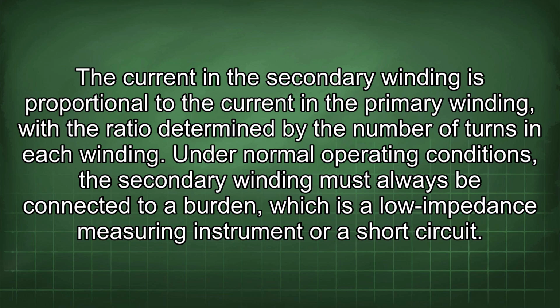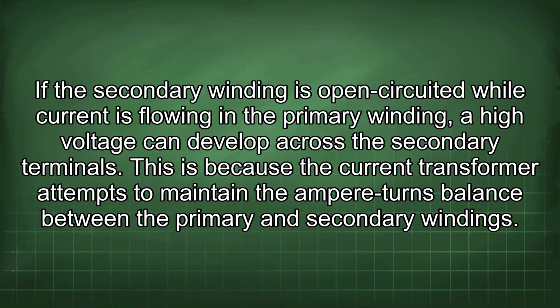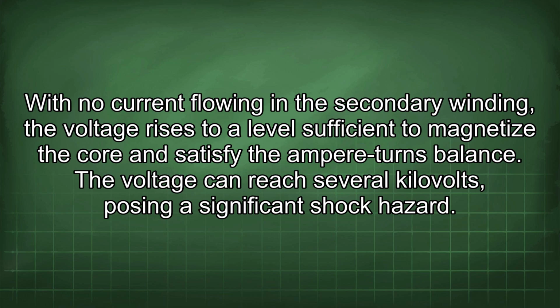Under normal operating conditions, the secondary winding must always be connected to a burden, which is a low impedance measuring instrument or a short circuit. If the secondary winding is open-circuited while current is flowing in the primary winding, a high voltage can develop across the secondary terminals. This is because the current transformer attempts to maintain the ampere-turns balance between the primary and secondary windings. With no current flowing in the secondary winding, the voltage rises to a level sufficient to magnetize the core and satisfy the ampere-turns balance. The voltage can reach several kilovolts, posing a significant shock hazard.